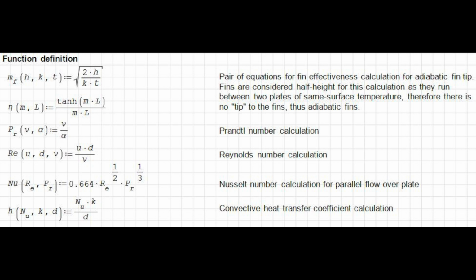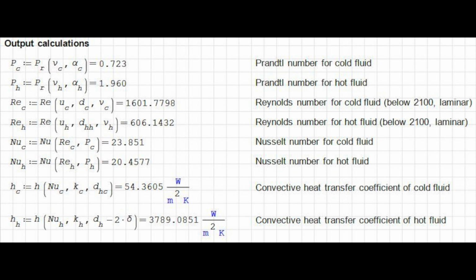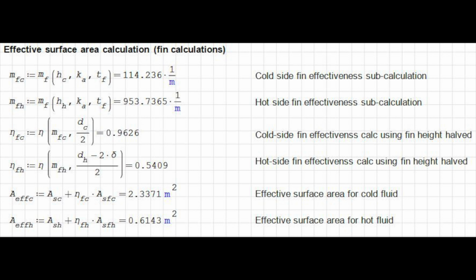This does get treated differently for the 19-row and 25-row dual pass ones, but we won't go over that calculation because, again, it's just the same thing as this, but you just treat the first and last row as full-length fins with non-adiabatic ends. Here is where we actually put the inputs together. So Prandtl number for cold fluid, Prandtl number for hot fluid, etc., etc. We move our way down here, we get all these numbers. Convective heat transfer coefficient for the hot and the cold fluids, M values and eta values for those. Those give us our correction factor for how well the fins actually work. So if you look here, the fins for the cold fluid are 96% effective of their actual surface area, while the hot fluid, they are more along the lines of 55% effective.